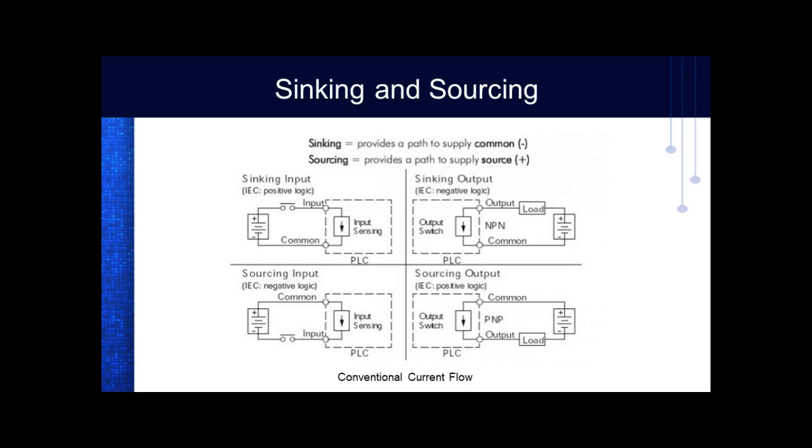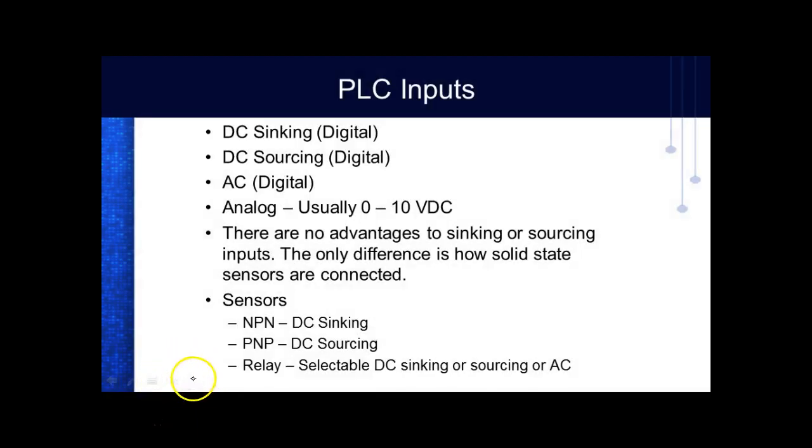You'll see, commonly over in the United States, and I'm not going to say you're never going to run into that, normally what we use on the PLC is where you see the input over here and you use sourcing out. That's just what we use over here. Now understand, sinking and sourcing only comes into play when you're dealing with DC, period. It has nothing to do with AC, because AC has no polarity.